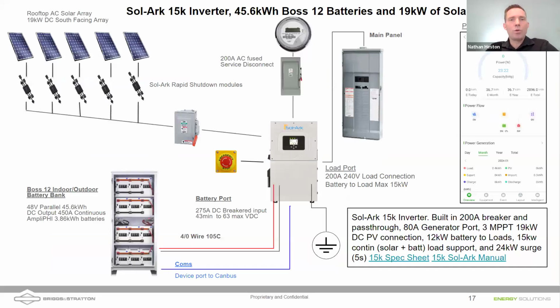Here's an example with a Sol-Ark 15k. The big difference here is being able to bring the power from the grid, right, from your meter through a fused disconnect into that inverter and being able to pass 200 amp service directly to your main panel. So this is a very nice feature of the Sol-Ark 15k, and I believe one of the big reasons why this inverter is so popular.